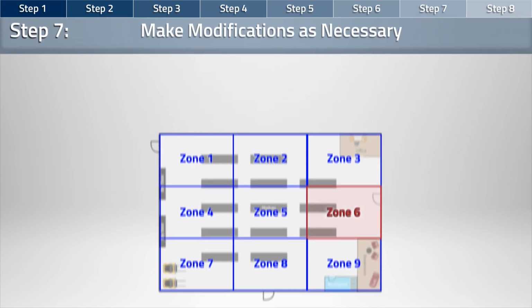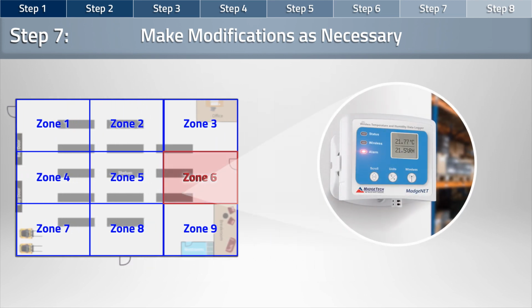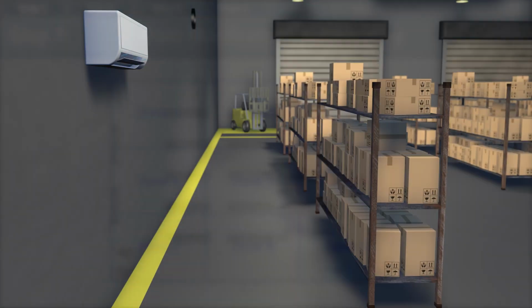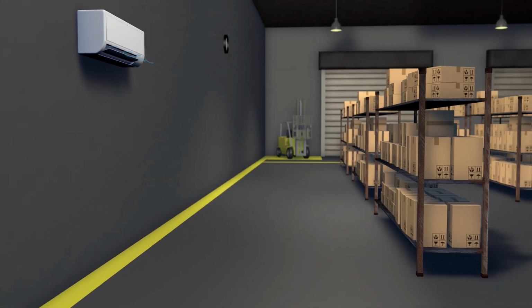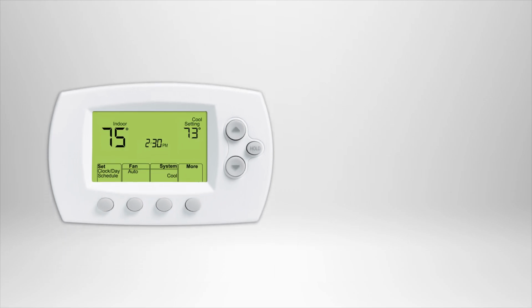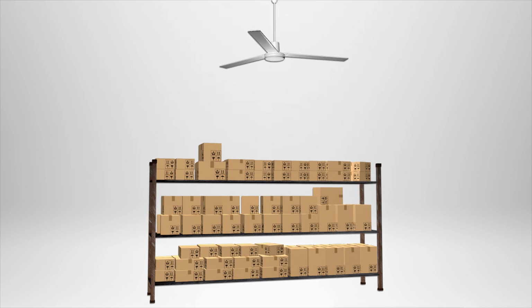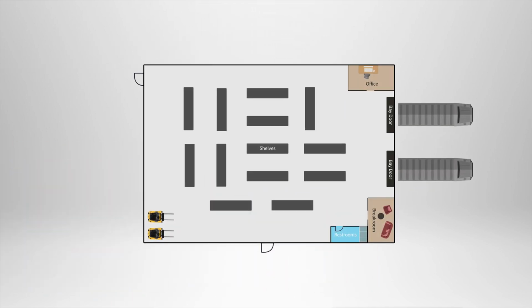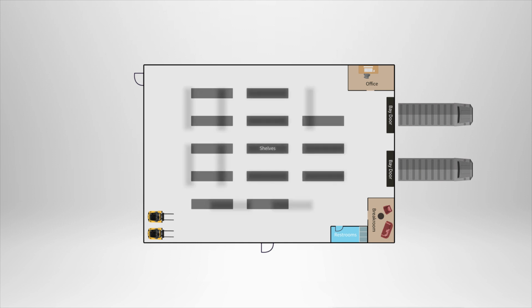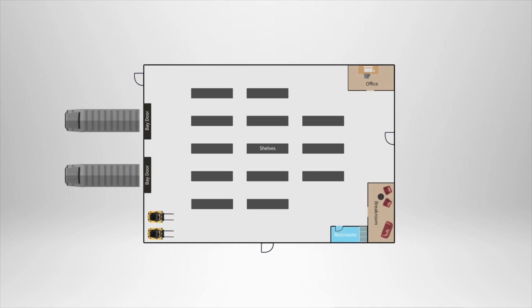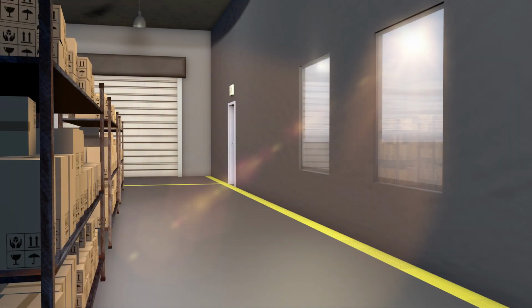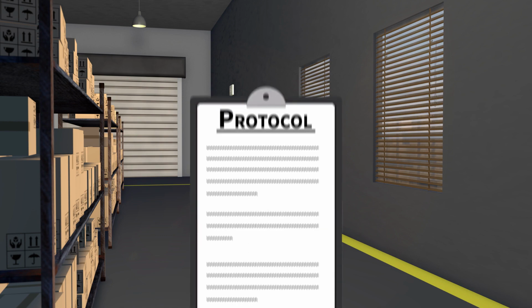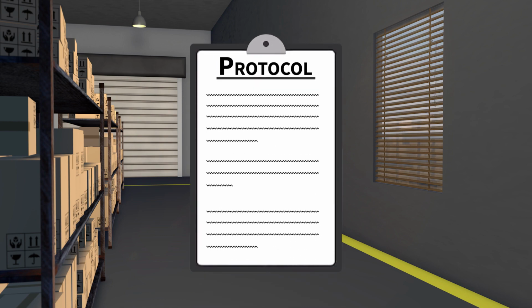After reviewing the data, you might find that some monitoring zones are breaching the threshold of desired readings. This means modifications must be made. Some common adjustments are moving racks that are too close to risk factors, adjusting HVAC settings or vent locations, adding fans to increase ventilation in certain areas, rearranging shelves to eliminate obstruction to airflow, addressing traffic to reduce opening and closing of doors in temperature-sensitive areas, or blocking sunlight that might be causing a hot zone. Each modification made should be documented in the protocol.